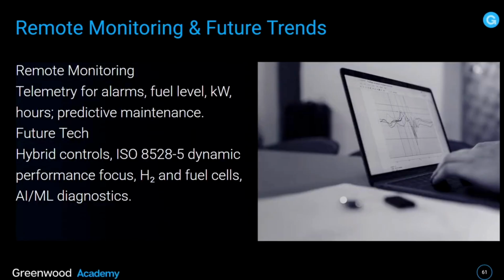This is a very interesting area where you're looking at predictive maintenance, and the ability to monitor the set in real time is becoming very, very important. It's better to be proactive when it comes to gensets than reactive, especially in situations where the genset is servicing critical loads. So remote monitoring, you're looking at telemetry for alarms, fuel level, kilowatt hours, and predictive maintenance. Now, future tech, hybrid controls, ISO 8528-5, dynamic performance focus, hydrogen fuel cells, AI, ML diagnostics.